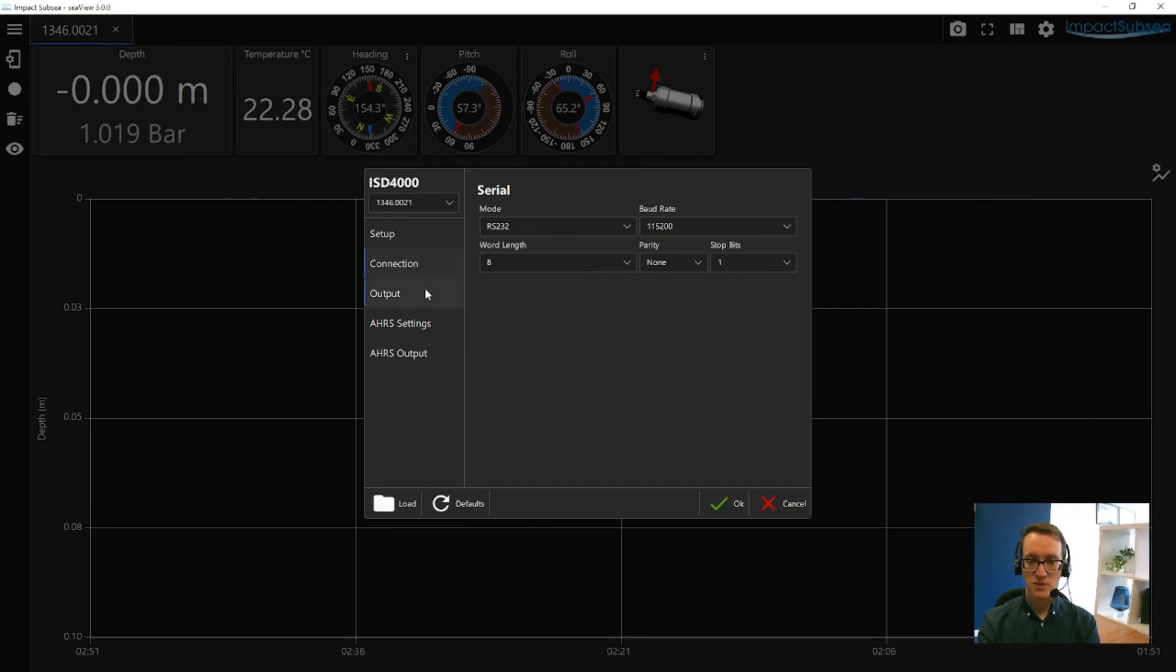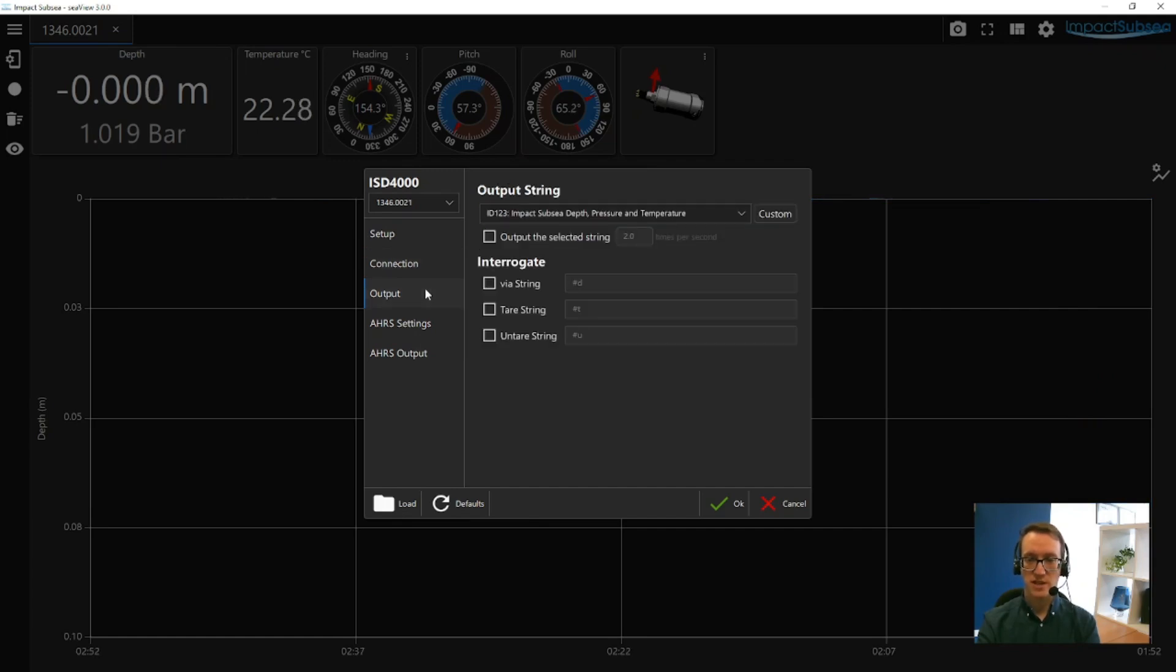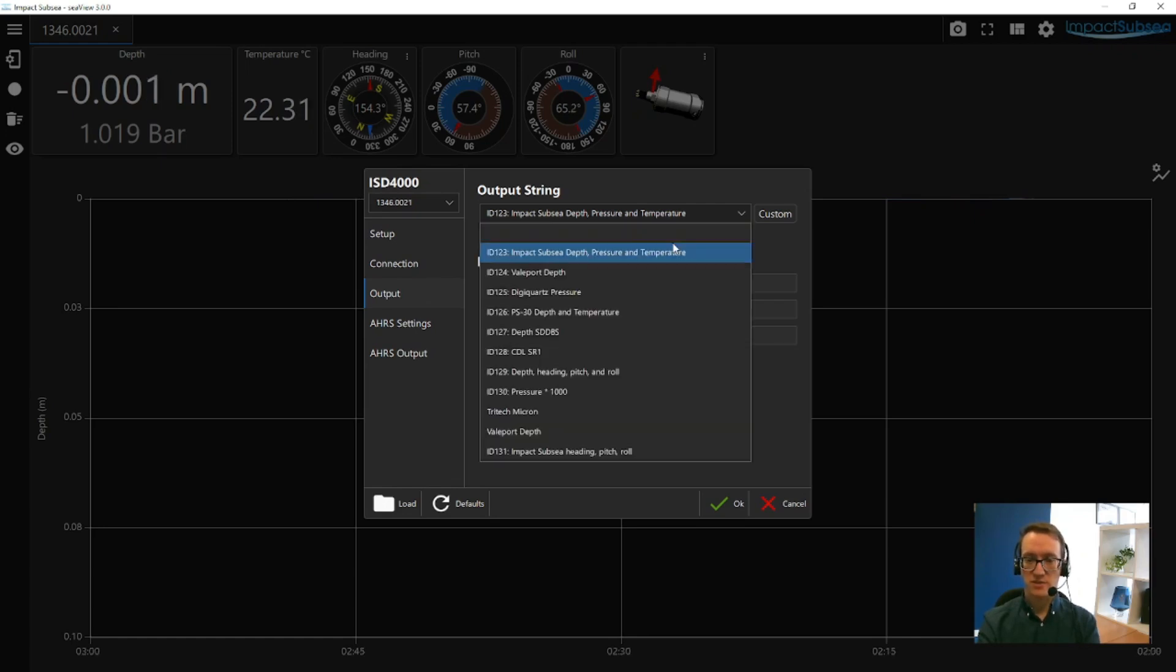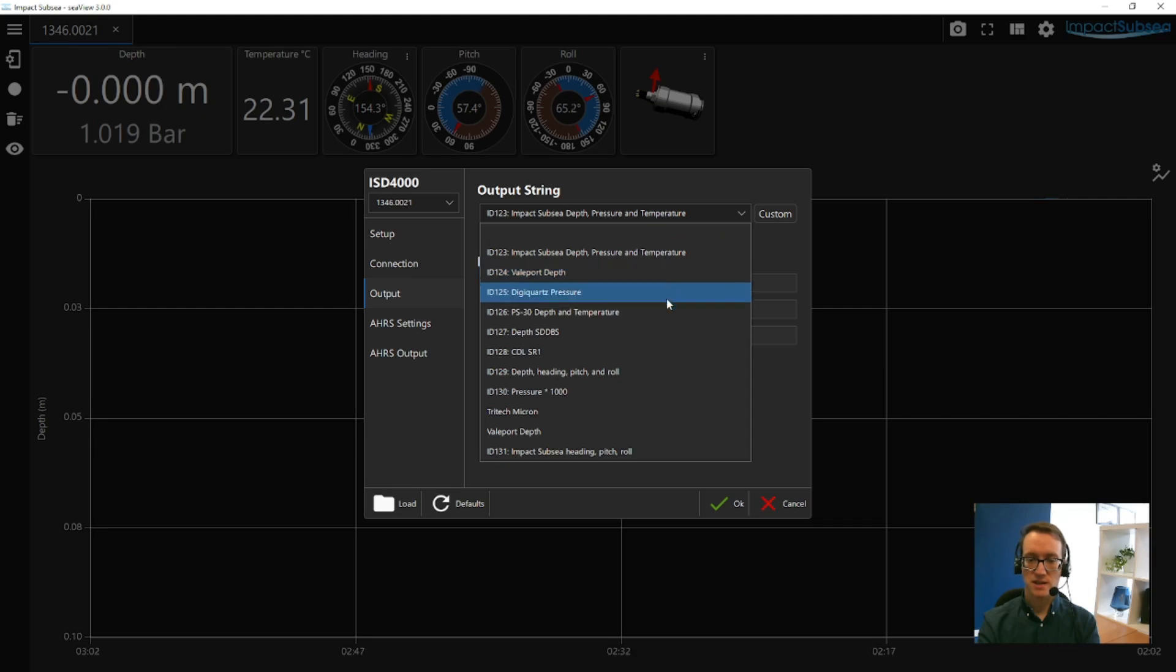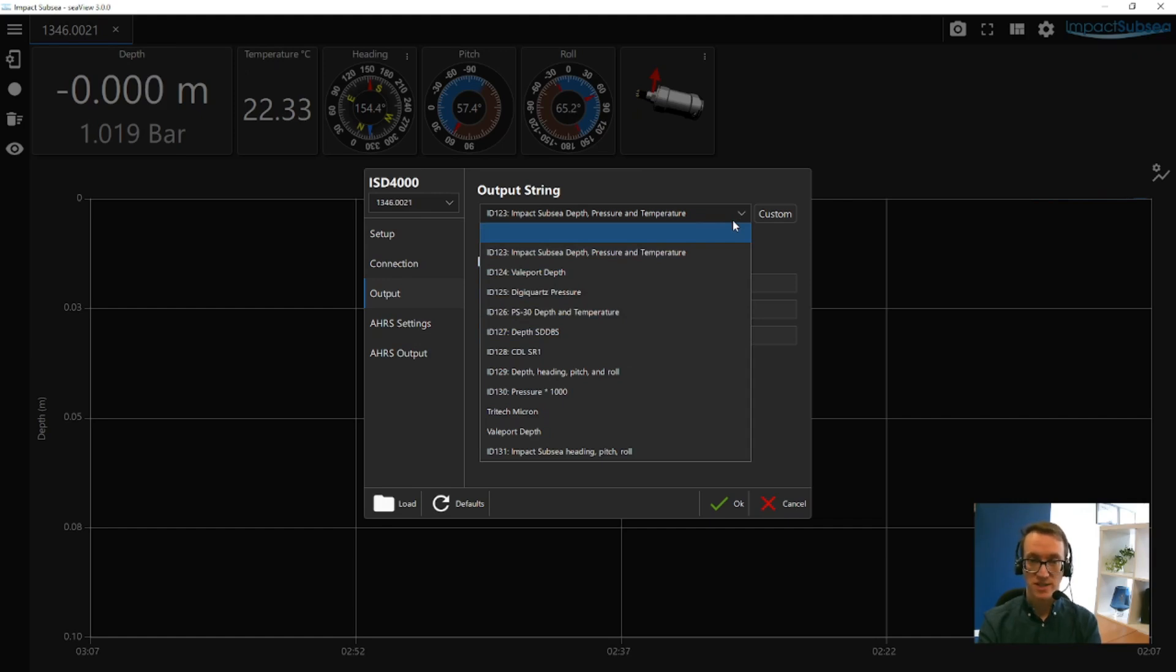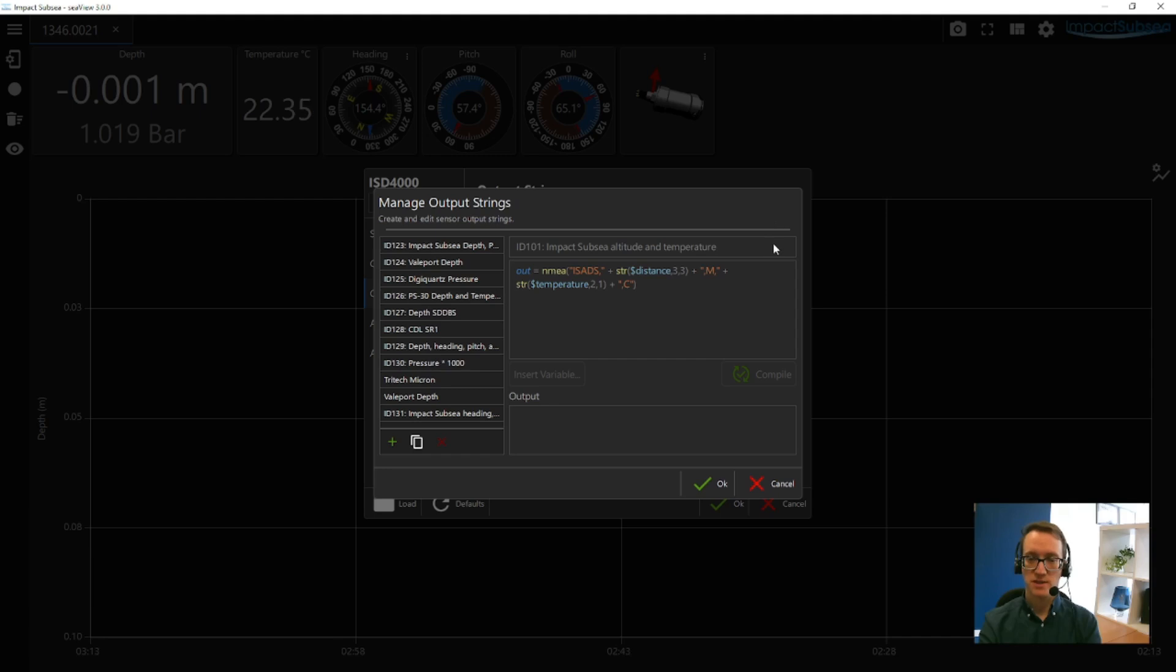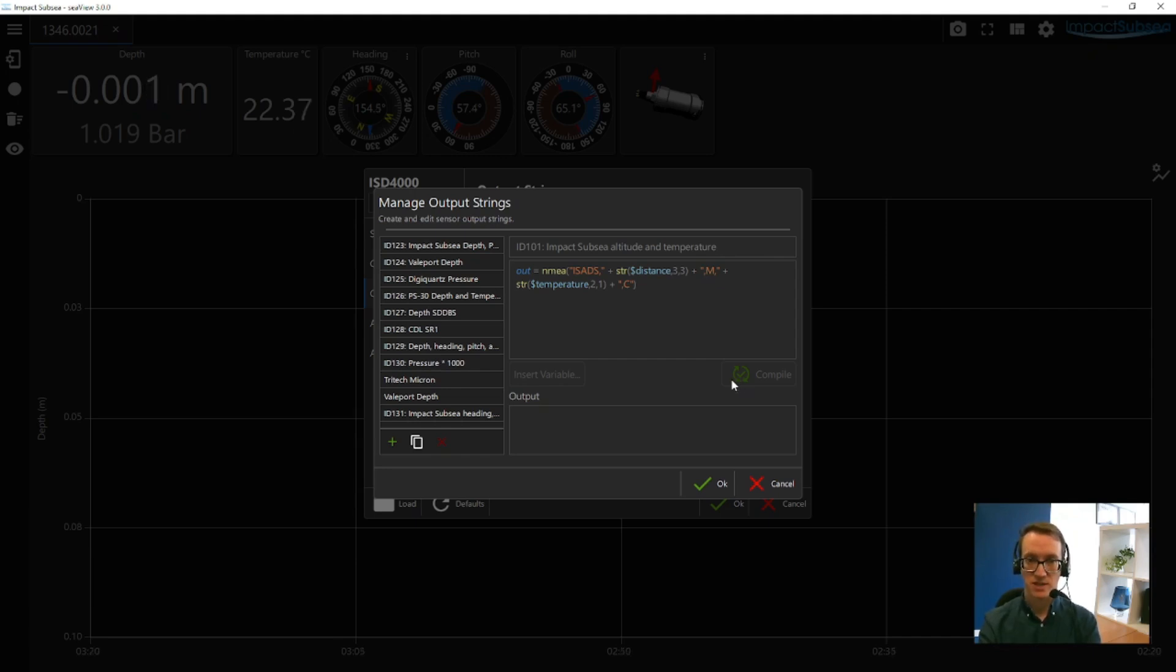And this next window allows you to set up the output string from the ISD4000. This is the output string for the depth and pressure. So there's a number of standard Impact Subsea strings and also a number of strings from other sensors as well. These are all documented fully in the ISD4000 manual. If there's a string you require which isn't present, you can use the custom button to either edit a string or add an entirely new ASCII output string to your own configuration. This makes the ISD4000 really simple and really easy to integrate with third-party systems.